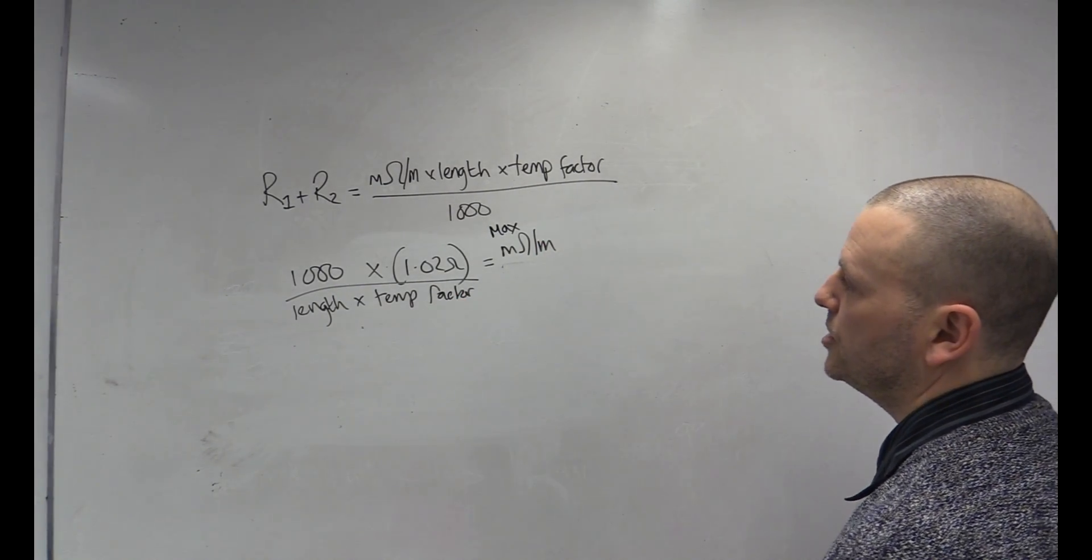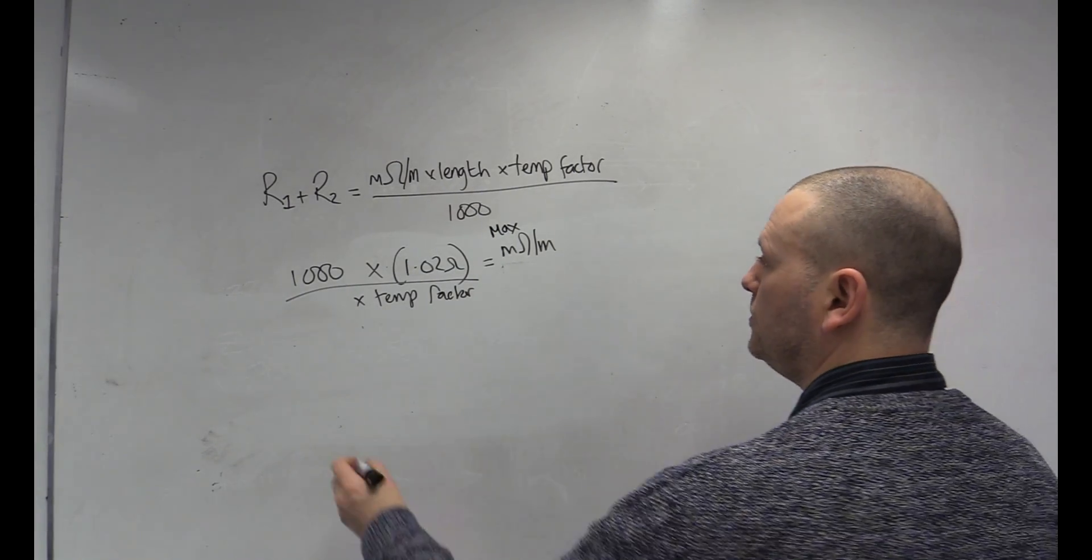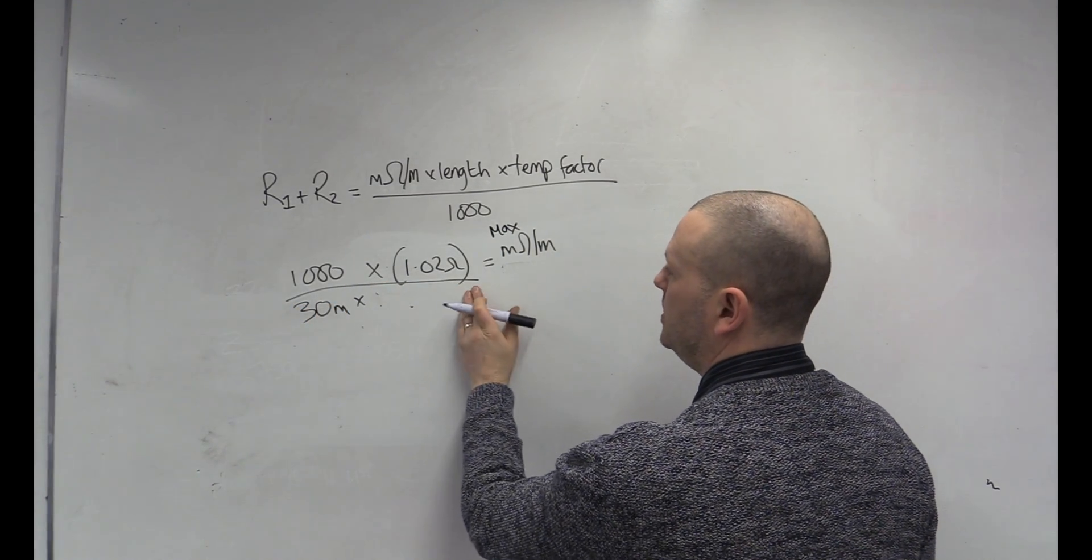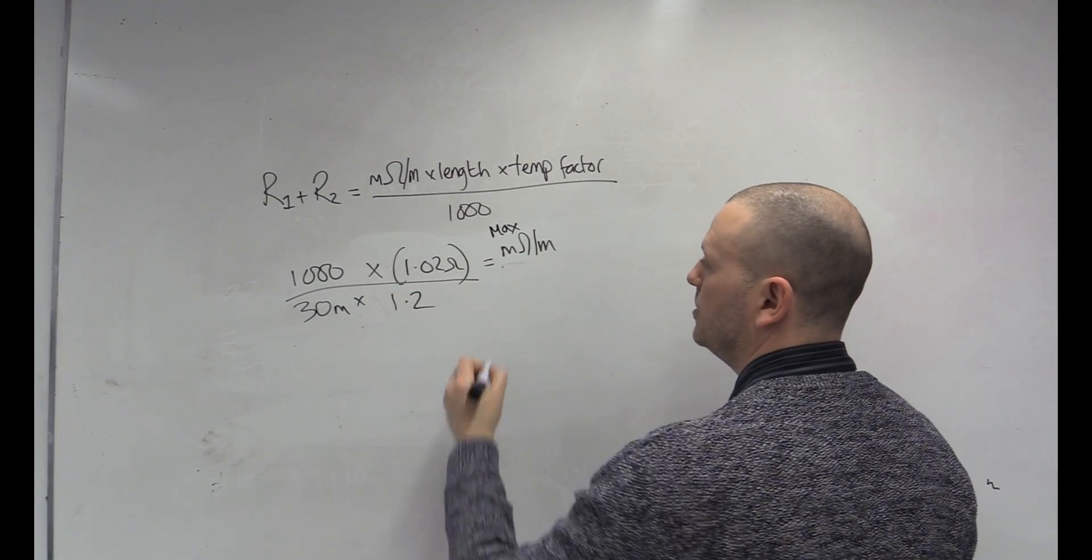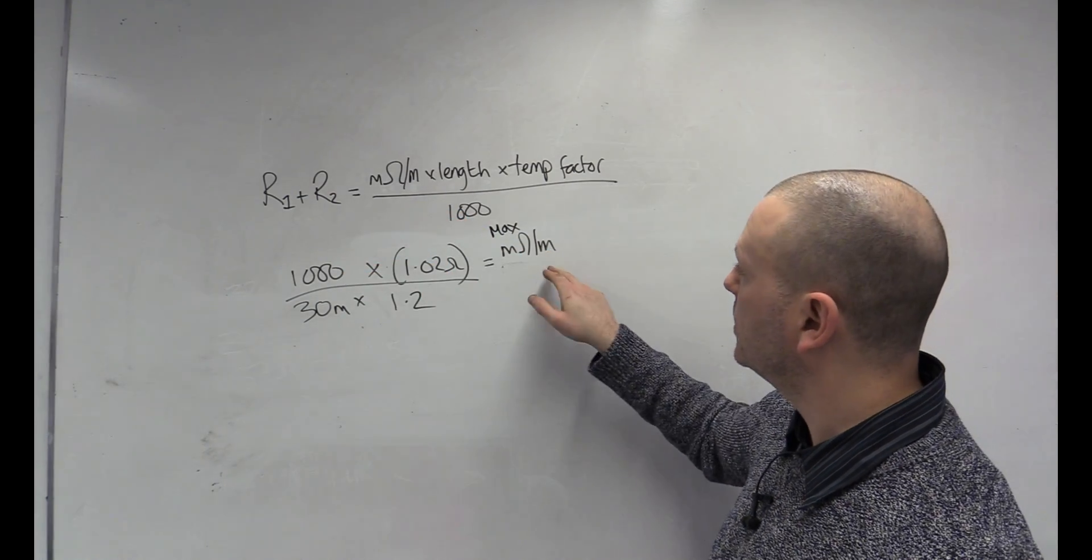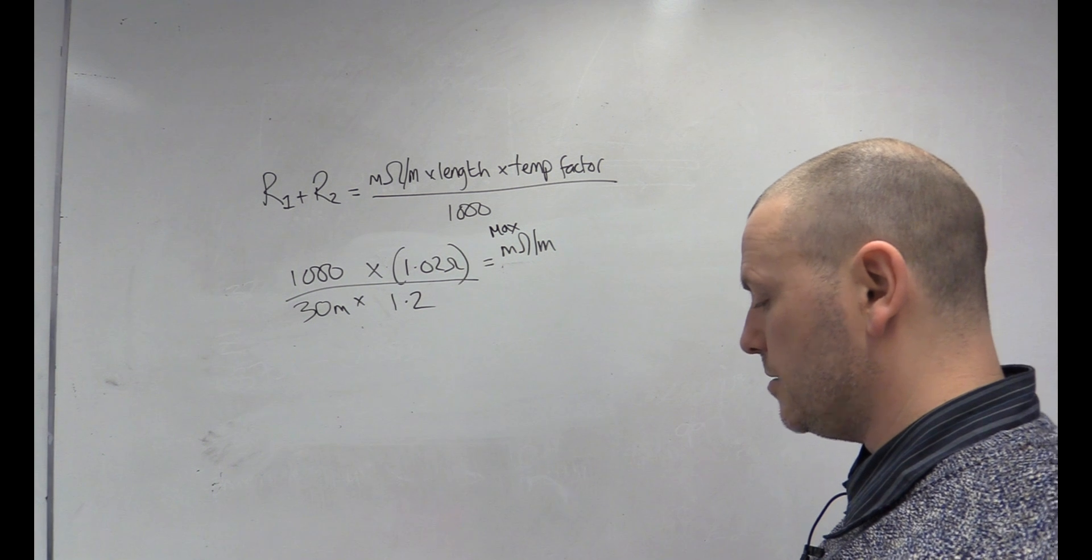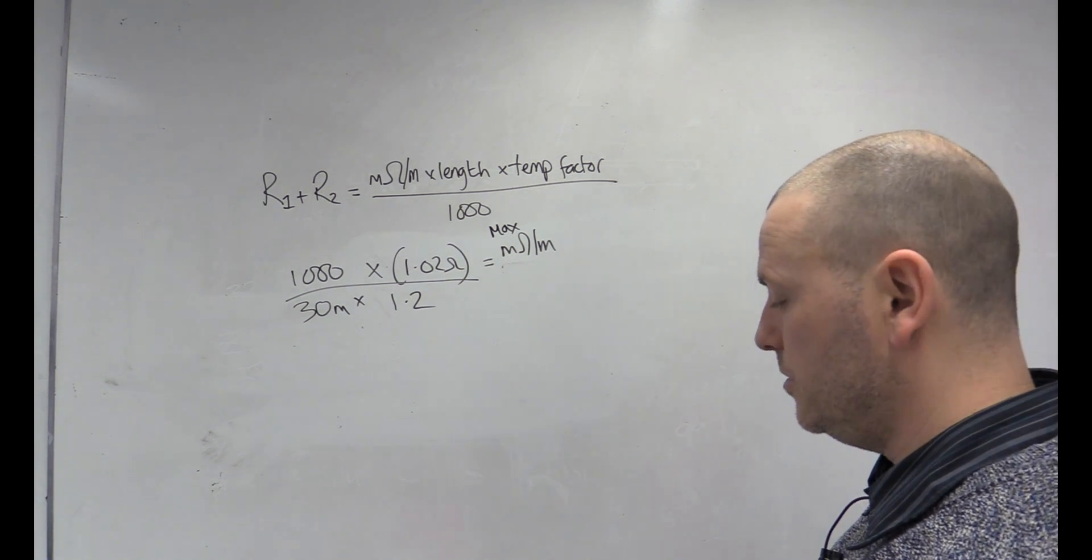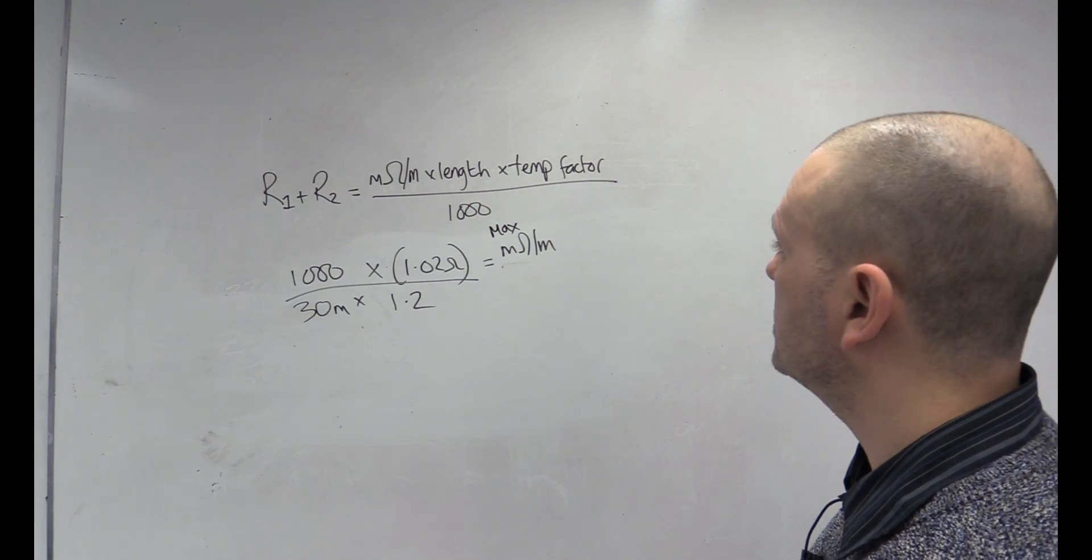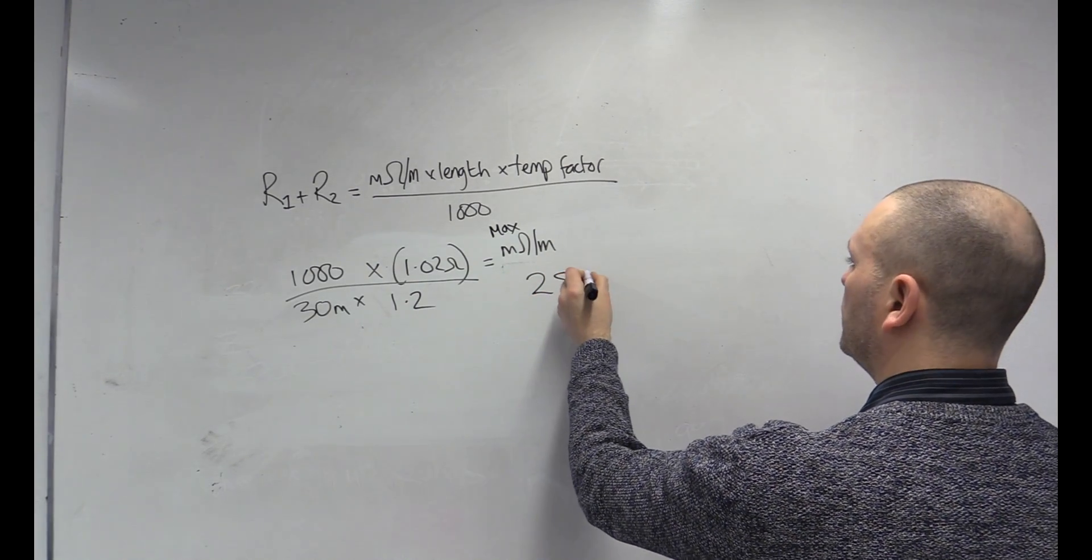So, shall we keep our length? Yes. 30 meters. And shall we keep our temp factor? Yes, because it's the same cable we're going to use at 1.2. Now, we've got numbers this side, so we can equate that and work out what our maximum milliohm per meter value is. So, 1,000 times 1.02 divided by 30 times 1.2 gives us a maximum milliohm per meter number at 28.33.